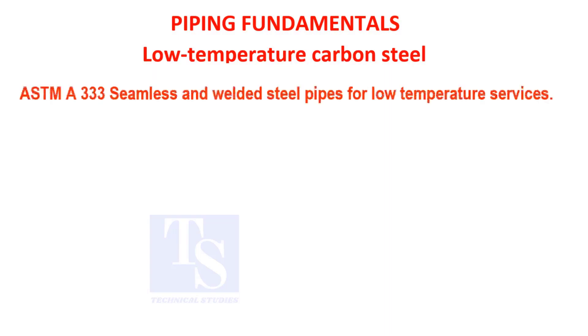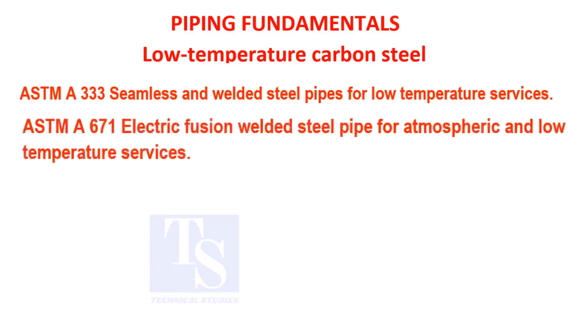ASTM A-333: seamless and welded steel pipe for low temperature services. ASTM A-671: electric fusion welded steel pipe for atmospheric and low temperature services. Available sizes are larger than 16 inches.